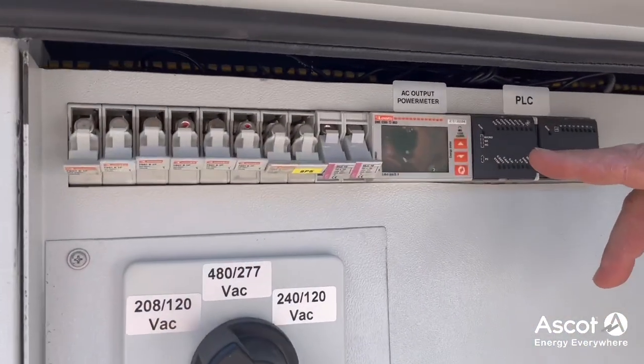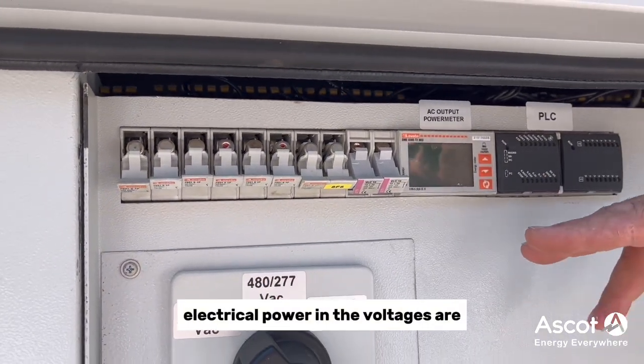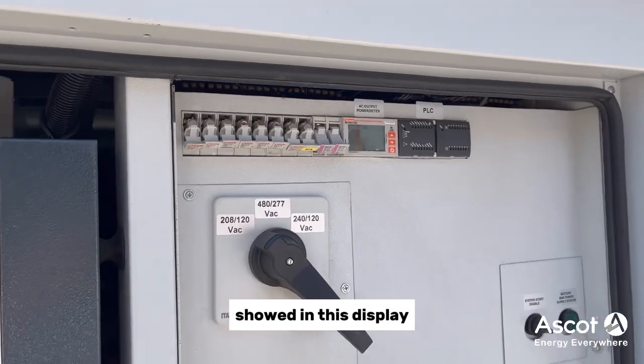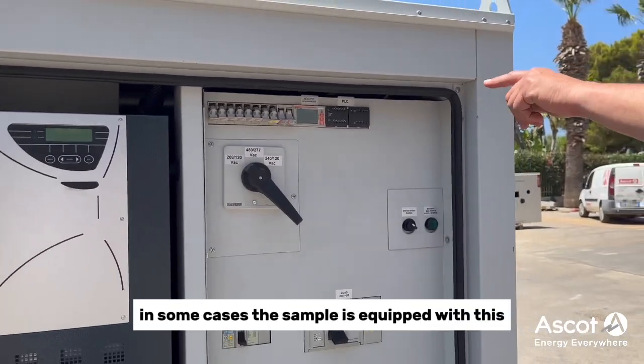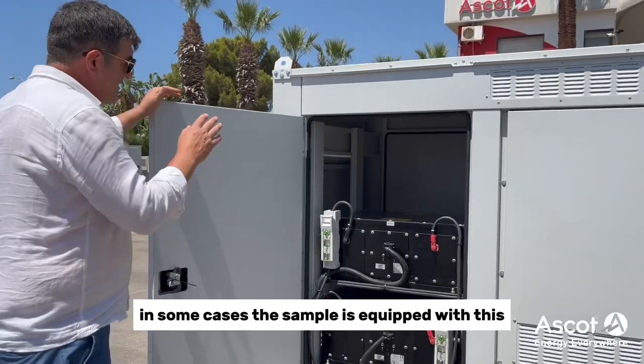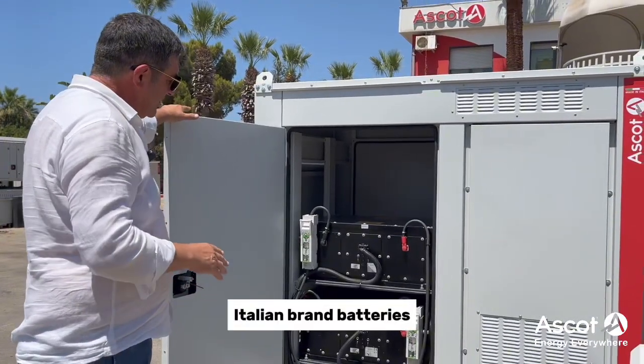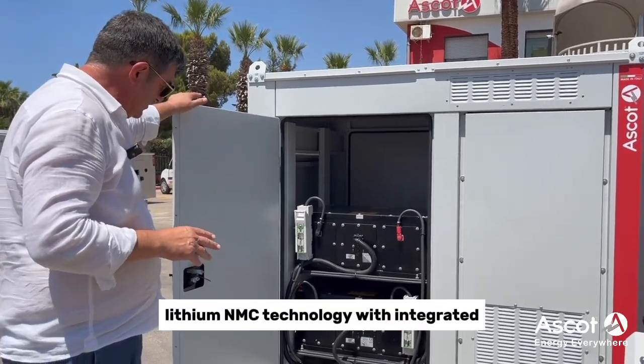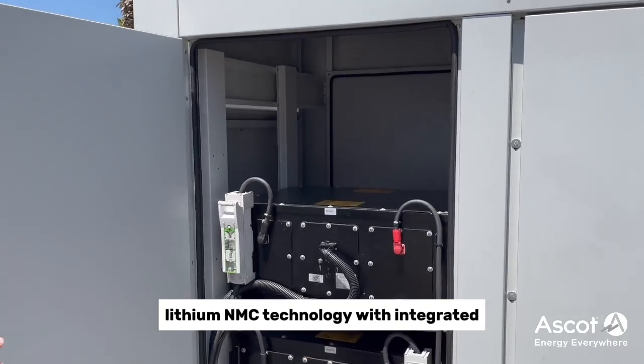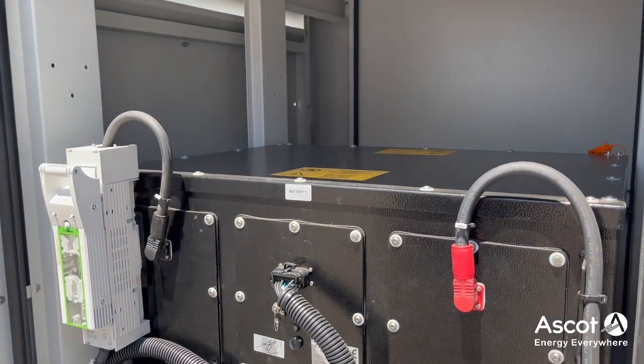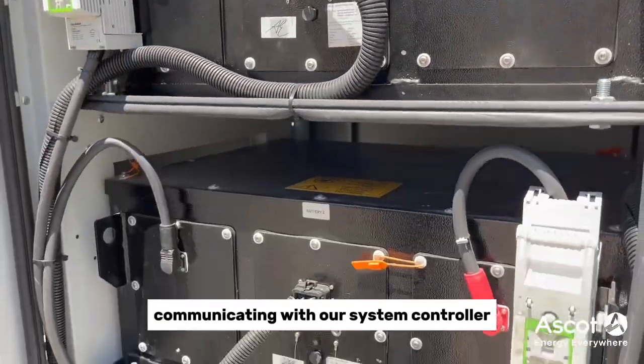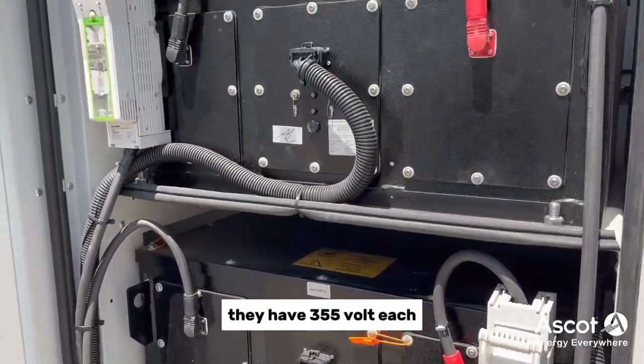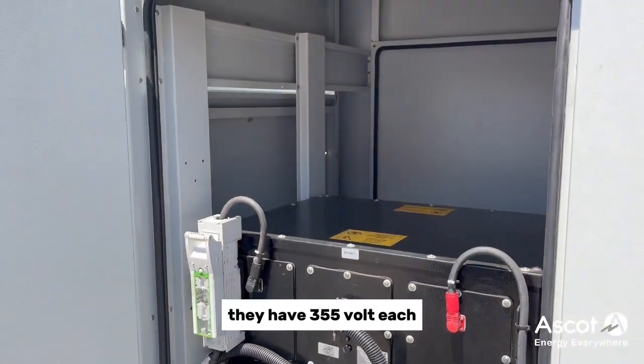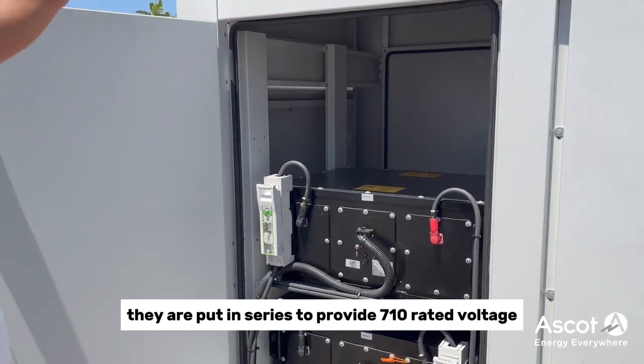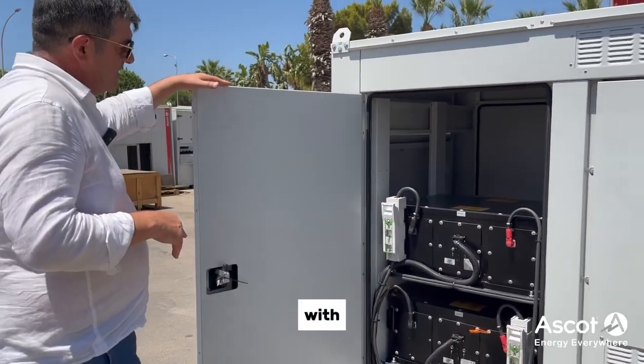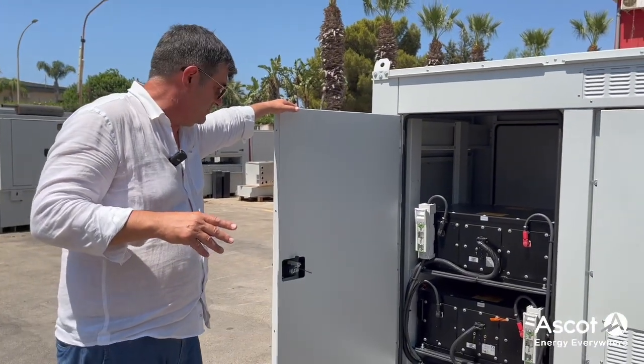All the electrical power and the voltages are shown in this display, as well as on the inverter display in some cases. The sample is equipped with these Italian brand batteries, lithium NMC technology, with an integrated embedded BMS communicating with our system controller. They are 355 volt each. They are put in series to provide 710 rated voltage with about 35 kilowatt hours capacity.